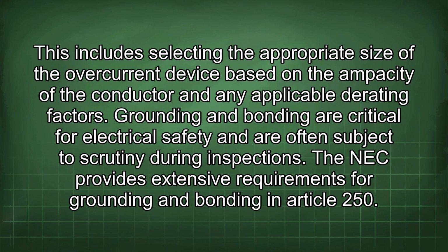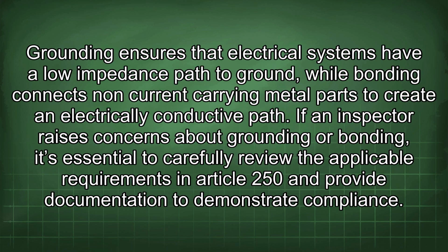Grounding and bonding are critical for electrical safety and are often subject to scrutiny during inspections. The NEC provides extensive requirements for grounding and bonding in Article 250. Grounding ensures that electrical systems have a low impedance path to ground, while bonding connects non-current-carrying metal parts to create an electrically conductive path. If an inspector raises concerns about grounding or bonding, it's essential to carefully review the applicable requirements in Article 250 and provide documentation to demonstrate compliance.